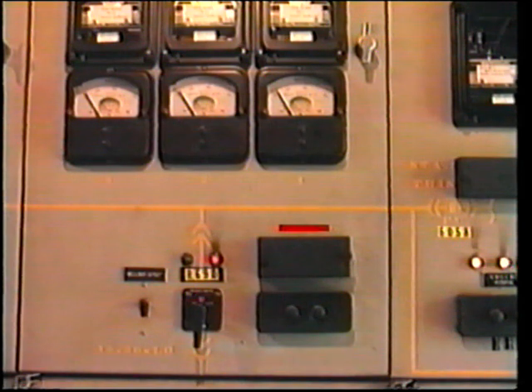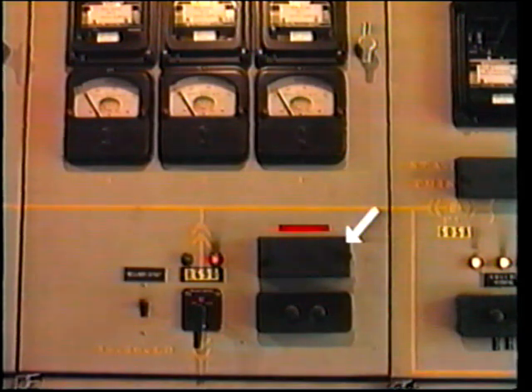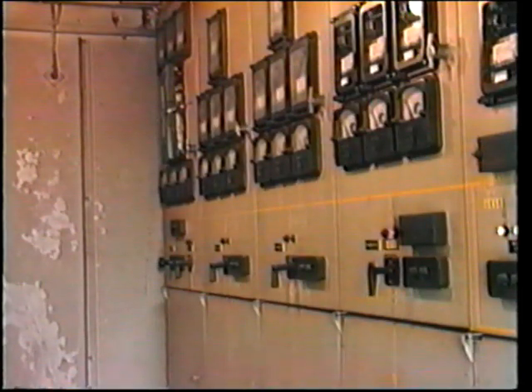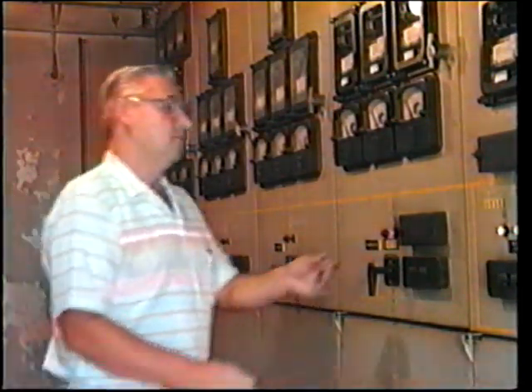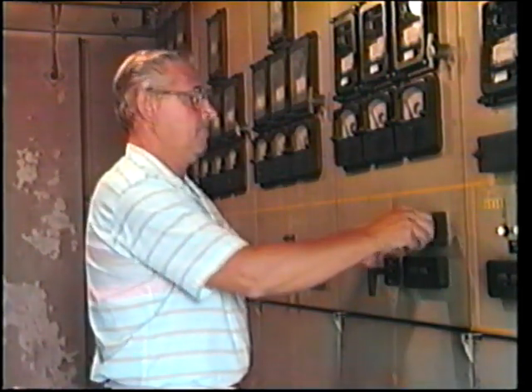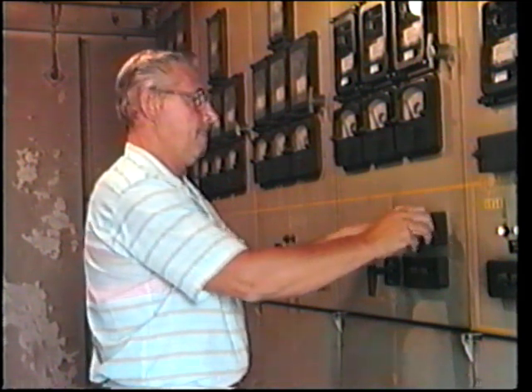Well, are you tired yet of these dismal stories? Let's look at just a couple more before we stop to draw some conclusions. In this particular occasion, a relay technician was performing in-service tests on a 133 kV line. This relay has a flexi-test switch mounted below. The technician removed the flexi-test switch cover and was preparing to insert the test jack into one current circuit.